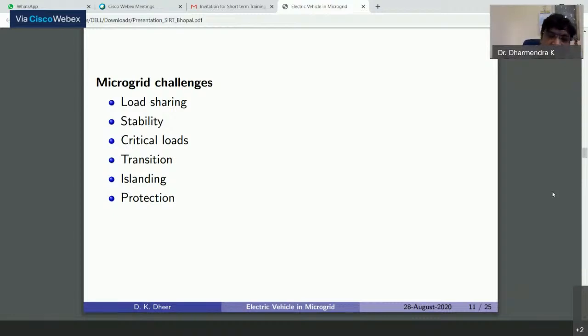And the major challenge is protection. How is it a major challenge? If there is a system which contains 3 generators, and now we have integrated 2 more generators into the system, so now there are 5 generators. Call this point A. Previously there was no generator there. Now one generator is connected to that point, and maybe some load changes also. The connection of this generator alters the fault current level. So random connection and disconnection of generators and loads in an islanded microgrid creates the protection challenge.